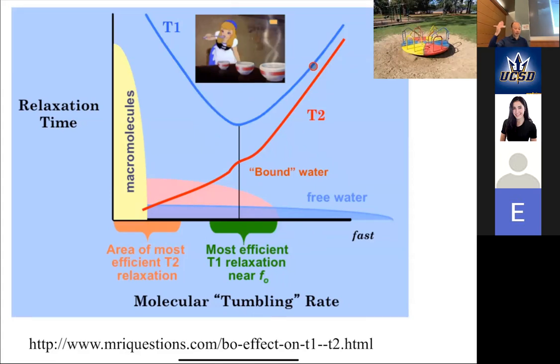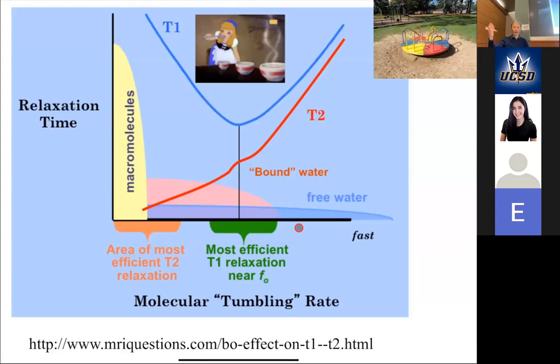You're only interacting with free water, which is not very good at letting you dissipate your energy, so T1 relaxation becomes less efficient. At 3 Tesla, T1 values are on the order of 1.5 seconds for many tissues. As people go to higher field strengths, T1 values get longer and longer. That's a trade-off: you're gaining SNR with higher field strength, but if you're waiting for the magnetization to recover, you're also losing some of that gain.